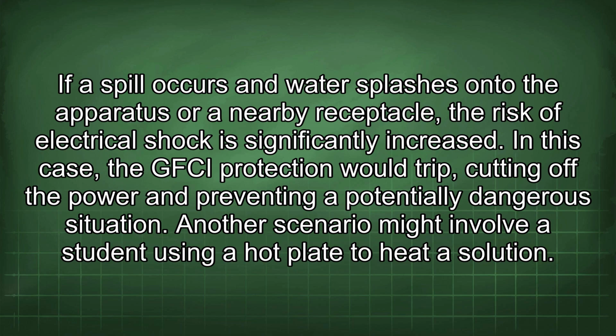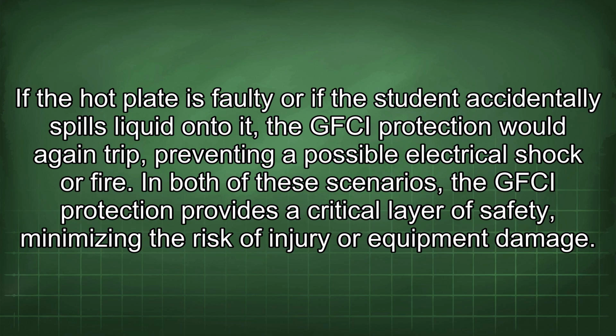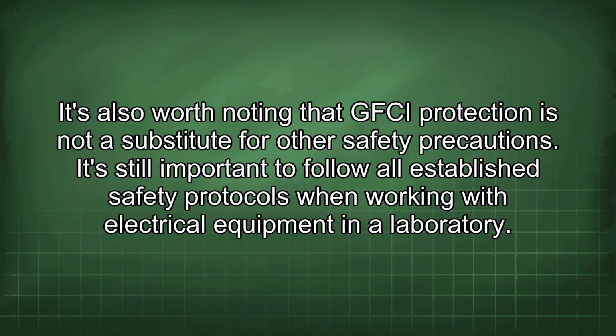Another scenario might involve a student using a hot plate to heat a solution. If the hot plate is faulty or if the student accidentally spills liquid onto it, the GFCI protection would again trip, preventing a possible electrical shock or fire. In both of these scenarios, the GFCI protection provides a critical layer of safety, minimizing the risk of injury or equipment damage. It's also worth noting that GFCI protection is not a substitute for other safety precautions.